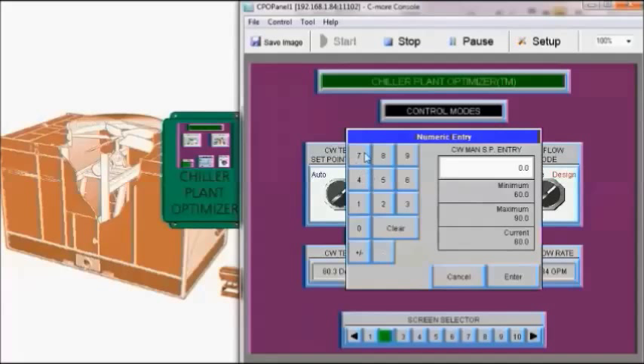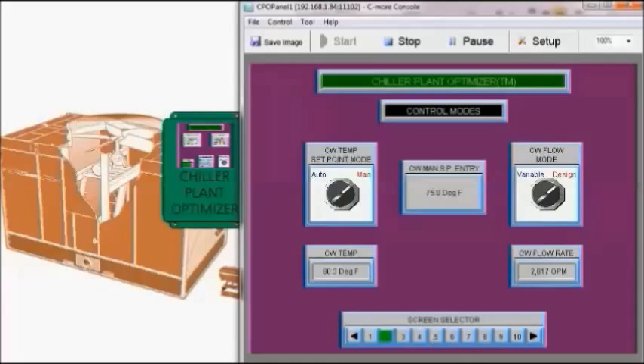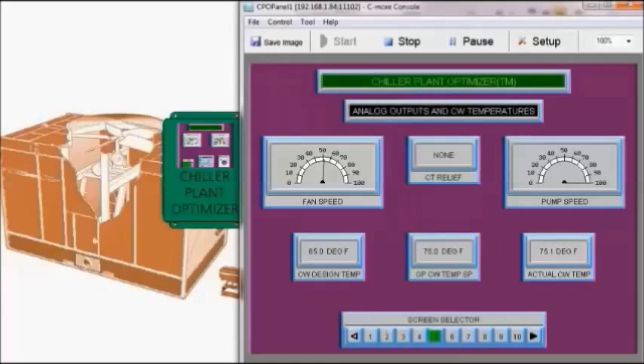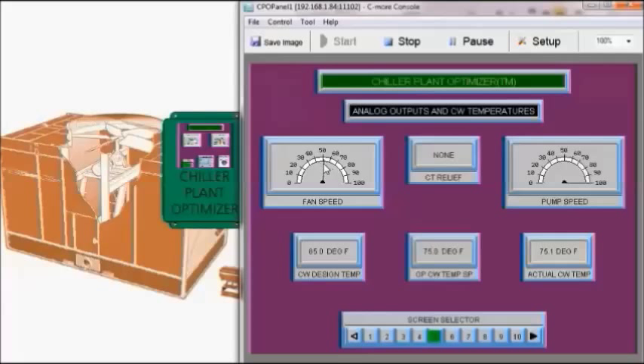So input 75 degrees as our manual condensed water temperature set point. So now with a 75 degree condensed water temperature set point, our fan speed is increased to about 51%, maybe 52%. And we're operating at 75.1 degrees condensed water temperature.